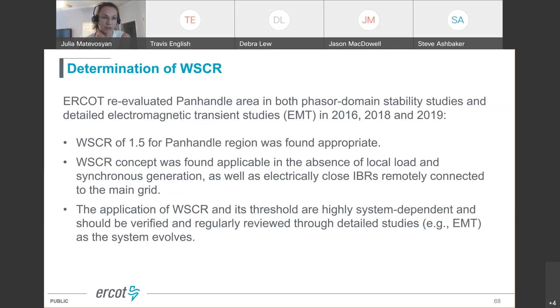So this is about 470 megawatt of load and 120 megawatt of synchronous generation, and this is located in the nearby Panhandle area. With interconnection of this part of the grid, we found that the weighted short circuit ratio concept cannot be easily used anymore. So you don't have this 1.5 metric that's readily applicable for all system conditions. Even though this area also helped to improve weak system strength concerns, on the other hand, because it brings load and synchronous generation in the area, applicability of this metric becomes blurred.